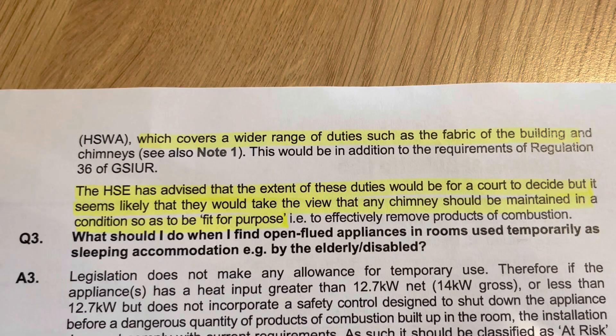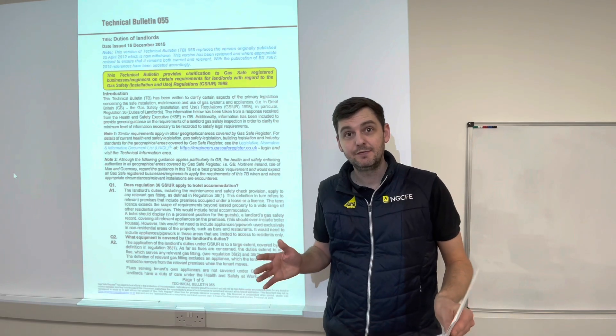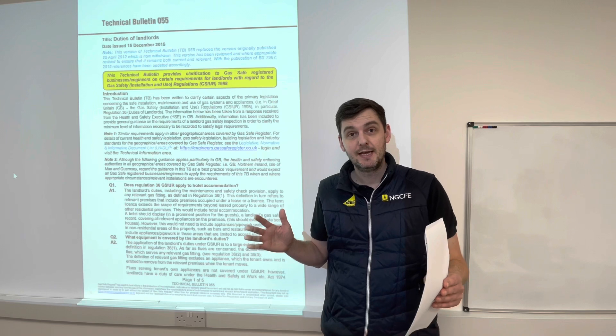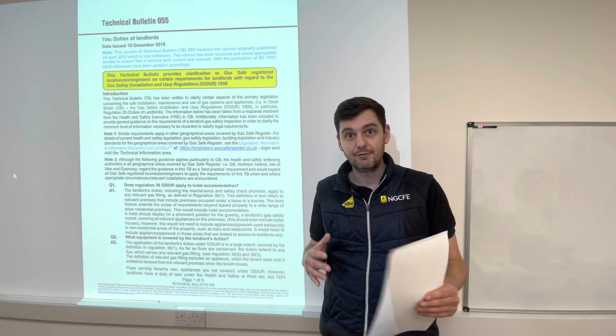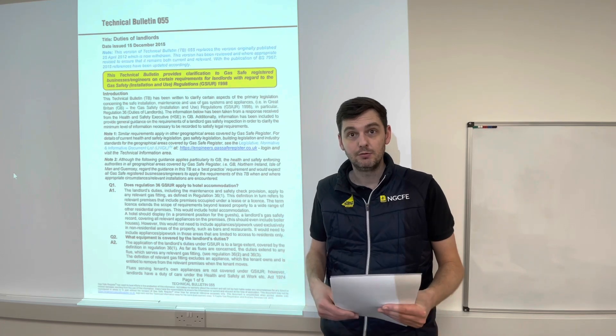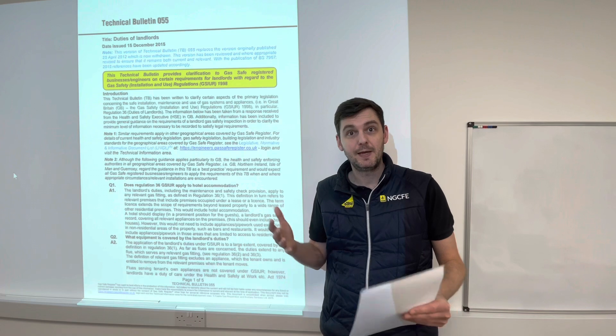The HSE has advised that the extent of these duties will be for a court to decide, but it seems likely that they would take the view that any chimney should be maintained in a condition so as to be fit for purpose. So if you've got a gas fire going into a brick chimney, although you're not necessarily required under the Gas Regs to check that chimney, you should really make sure that chimney is fit for purpose.